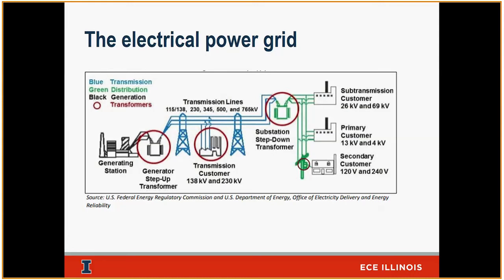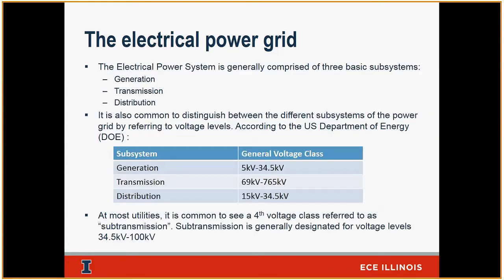Higher voltage, because you want to avoid, of course, losses. Losses are a function of I squared R, and the more I you have, the more losses you've got. So we try to send energy over the transmission lines at a higher voltage to reduce these losses. As you get closer to the community, you start stepping the voltage down, and we go from the transmission level world to the distribution level world. Typically, the substations are, again, less than 100 kV. When you get to that level, we break them down into two sub-levels. We call one a sub-transmission level, and we call the other a distribution level.